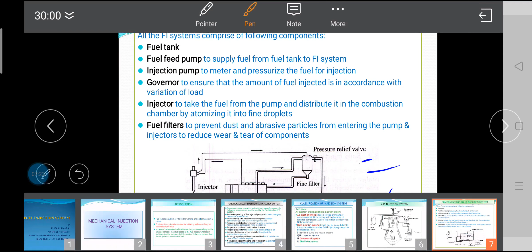Fuel from the fuel tank first enters the coarse filter, from which it is drawn into the plunger feed pump, where the pressure is raised very slightly. Then the fuel enters the fine filter, where all the dust and dirt particles are removed. From the fine filter, the fuel enters the fuel pump, where it is pressurized to about 200 bar and injected into the engine cylinder by means of the fuel injector.